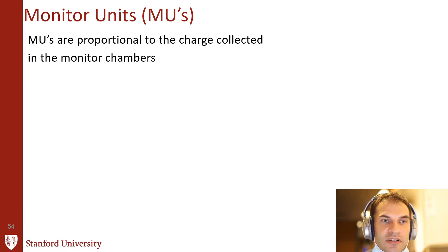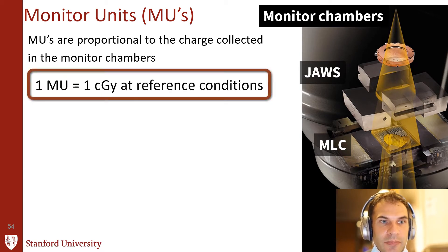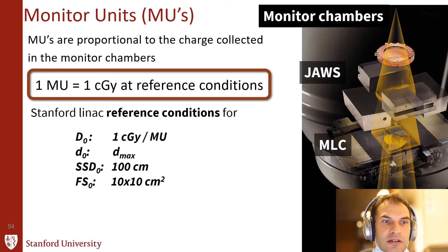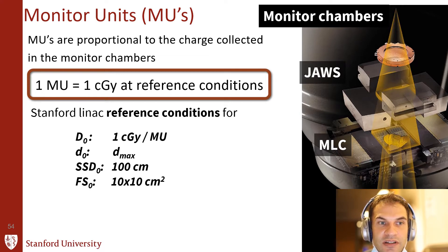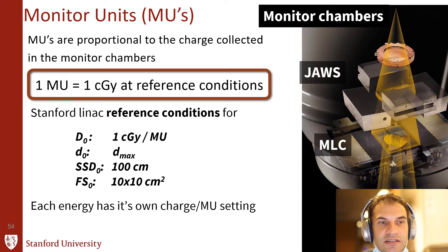Monitor units are proportional to the charge collected in the monitor chambers. The job of the monitor chambers is to make sure the radiation coming out of the machine is at a constant dose rate. One monitor unit is 1 centigray at reference conditions. At Stanford, our reference conditions are 1 centigray at 1 MU at D-max — the depth of maximum dose in water — at SSD 100, 10 by 10 field size. Each energy has its own charge per MU settings and is independently calibrated.